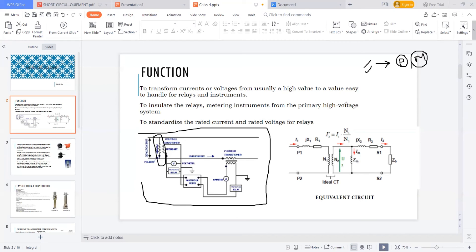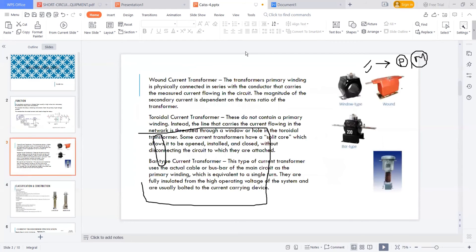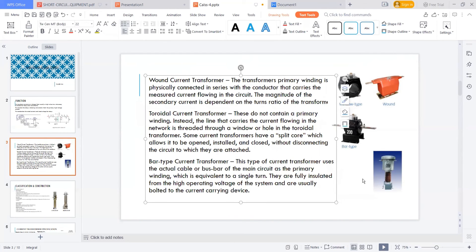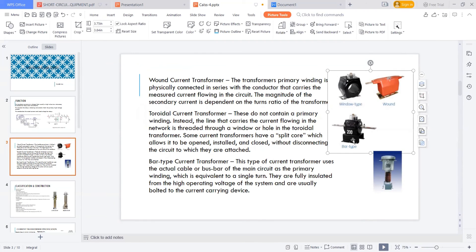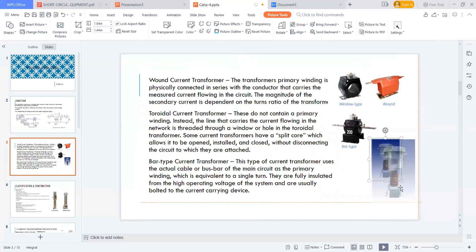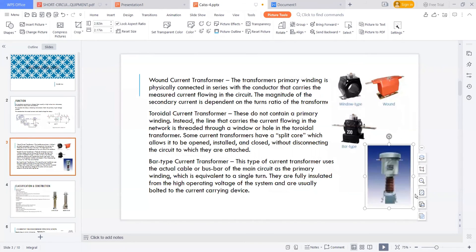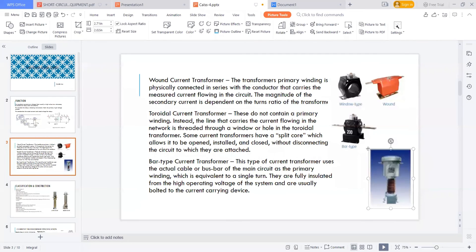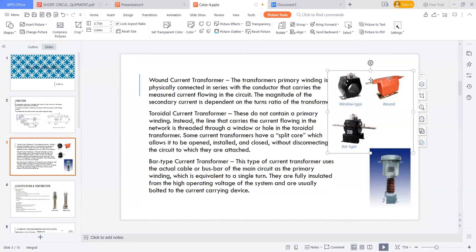Now let's go to the current transformer first, followed by the potential transformer. We have three or four types of current transformers. In low voltage applications you mostly see window transformers, wound transformers, or bar-type transformers. In substations you see conventional transformers — oil tank type, live tank, or dead tank current transformers. Our analysis will be with respect to substation design, so we will figure out the sizing, selection, and calculation, which remain the same for all types.